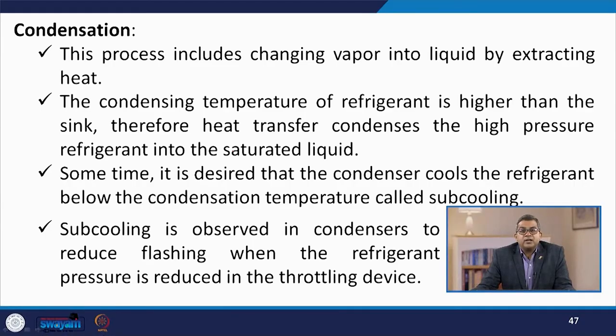The condensation process involves changing vapor into liquid by extracting heat. Whatever heat was absorbed, plus the work carried out through the compressor, must be extracted. The condensing temperature of the refrigerant is higher than the sink; therefore, heat transfer condenses the high pressure refrigerant into saturated liquid. Sometimes it is desired that the condenser cool the refrigerant below the condensation temperature — called subcooling. Subcooling in the condenser reduces flashing when the refrigerant pressure is reduced in the throttling device.